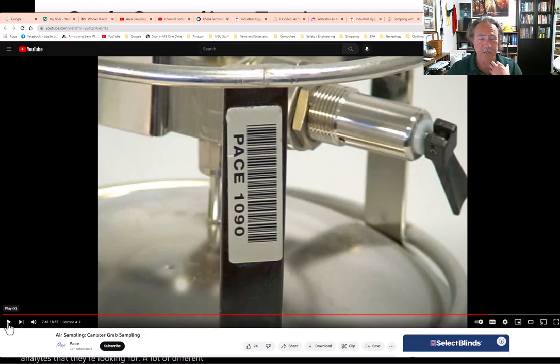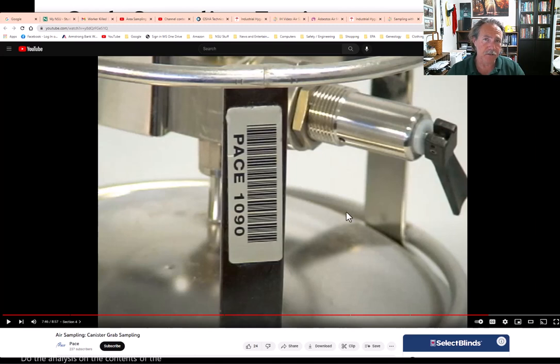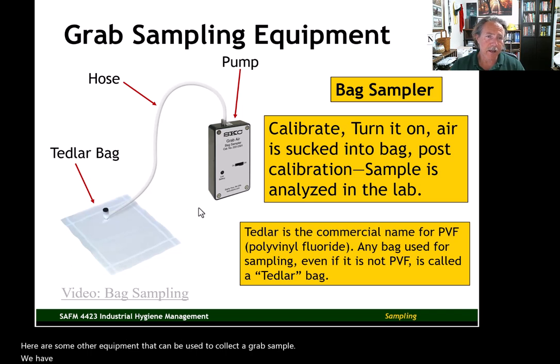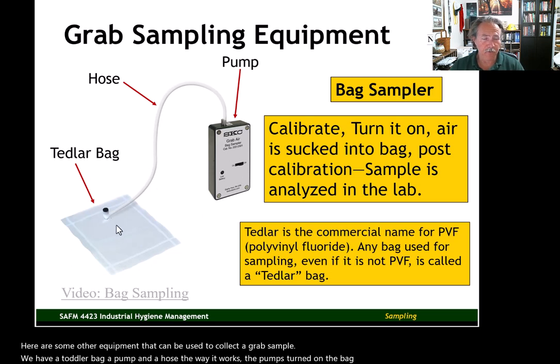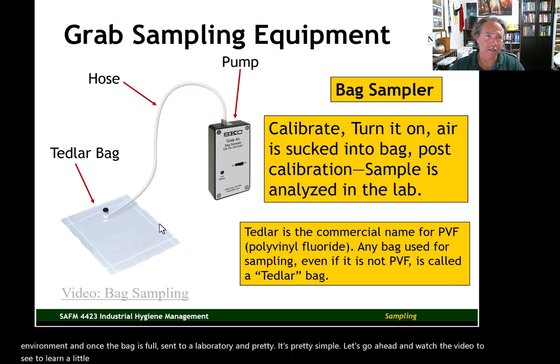There can be a lot of different analytical methods used depending on the analytes they're looking for — flame ionization detector, gas chromatograph technology can be used to analyze the contents of the canister. Here is some other equipment that can be used to collect a grab sample: a Tedlar bag, a pump, and a hose. The pump is turned on, the bag fills up with air from the work environment, and once the bag is full it's sent to a laboratory.